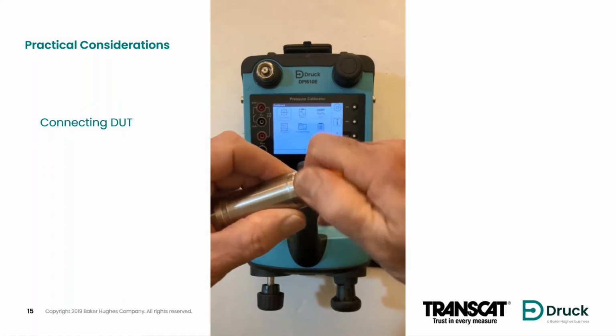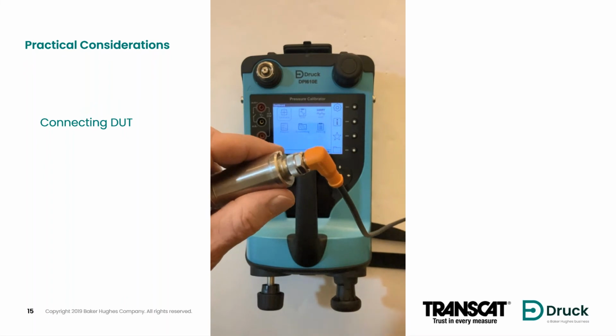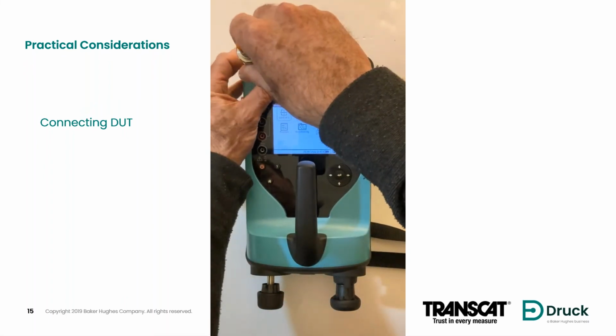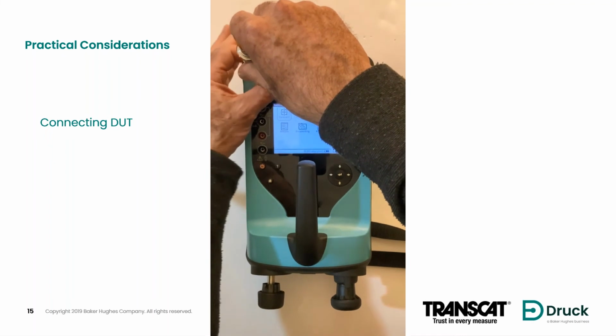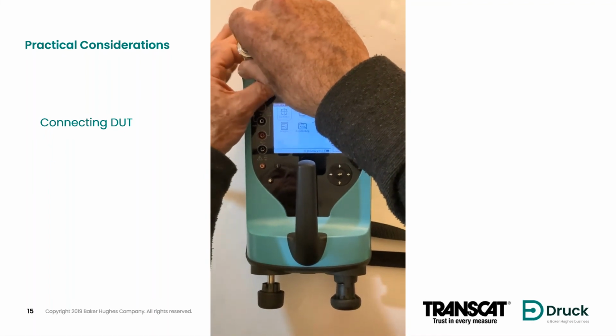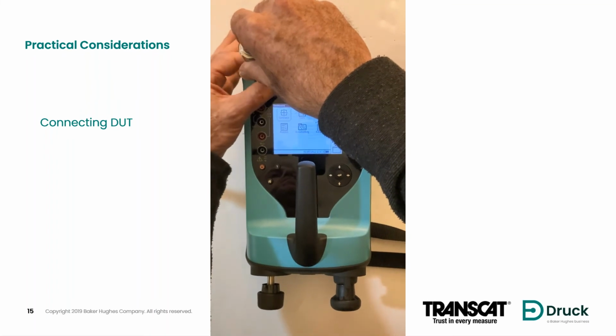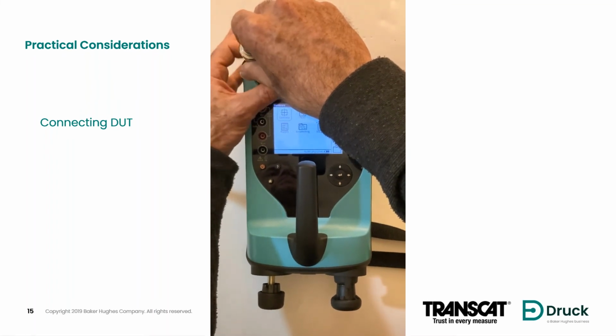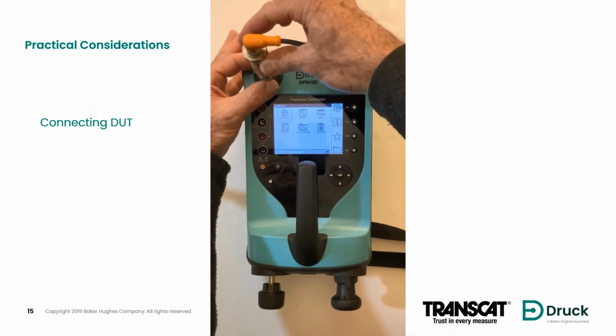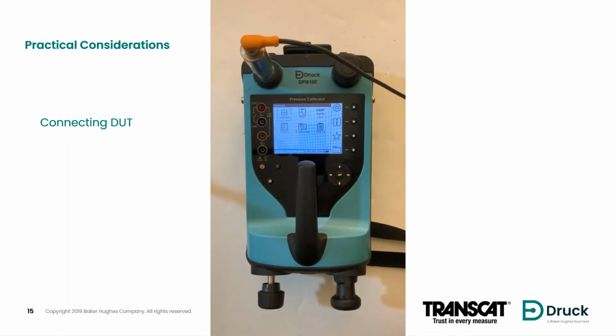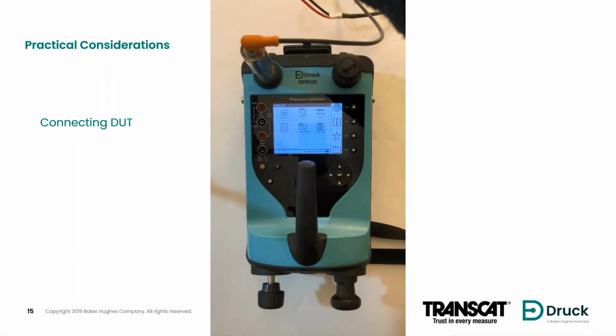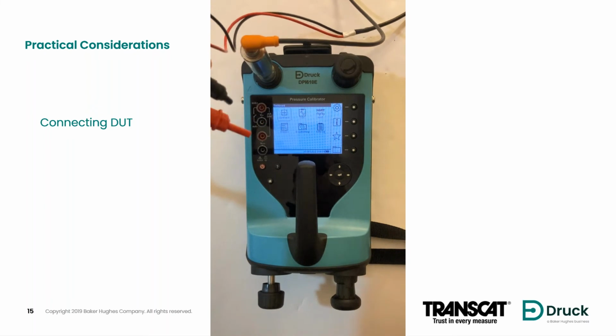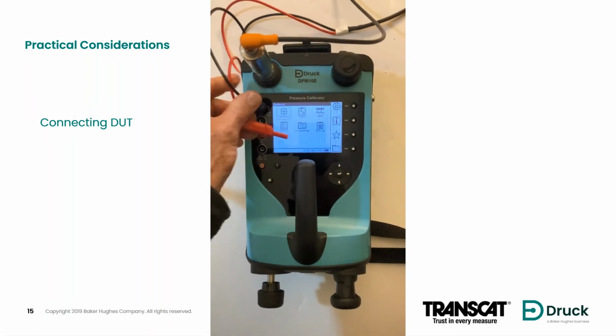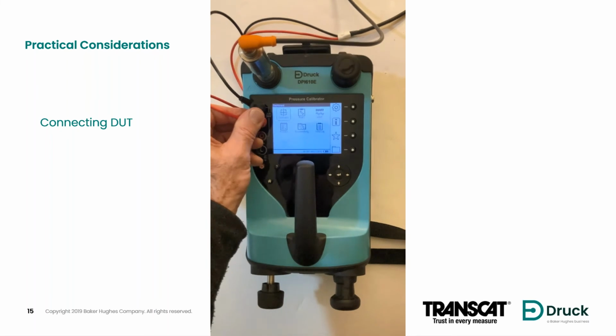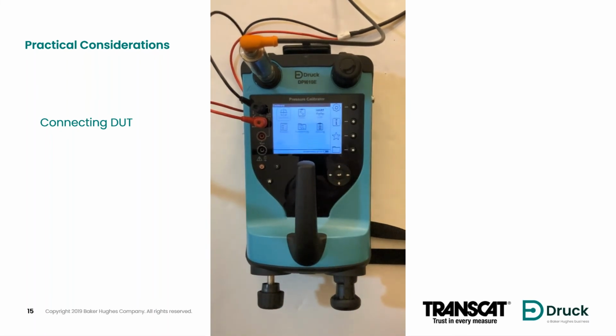So one of the considerations, you want to have a system that's easy to set up. We have a swivel bezel nut that rotates around the device under test rather than having to rotate the device under test around a fixed test port. And there's a piston seal arrangement there, so there's no flats on it. So you'll notice that was finger tight, and it's finger tight good up to 15,000 PSI. So here I'm making the connections to the electrical ports. So pretty quick and simple setup, hopefully.